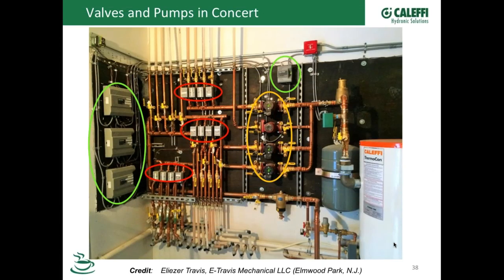I can probably jump in on that one for you, Bob. When I was in the field, we did a lot of systems with buffer tanks because we were doing a lot of small zones and wanted to make sure the boiler wasn't short cycling. In a lot of those cases, we used Alpha circulators along with the Caleffi zone valves. We would let everything on the system side of that buffer tank operate as normal, pulling heat from the buffer tank, while the pump from the boiler to the buffer tank would shut down, and then your pump from the boiler to the indirect tank would fire up. So by shutting down that circulator between the boiler and the buffer tank, you're not affecting it in any way, and the boiler can heat the indirect and do what it needs to do.